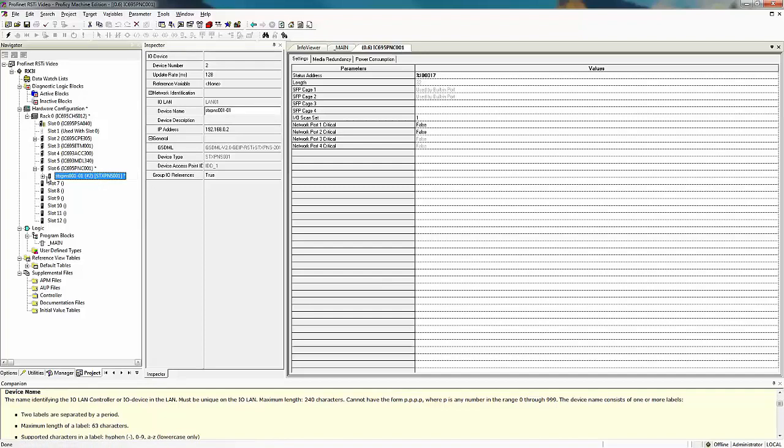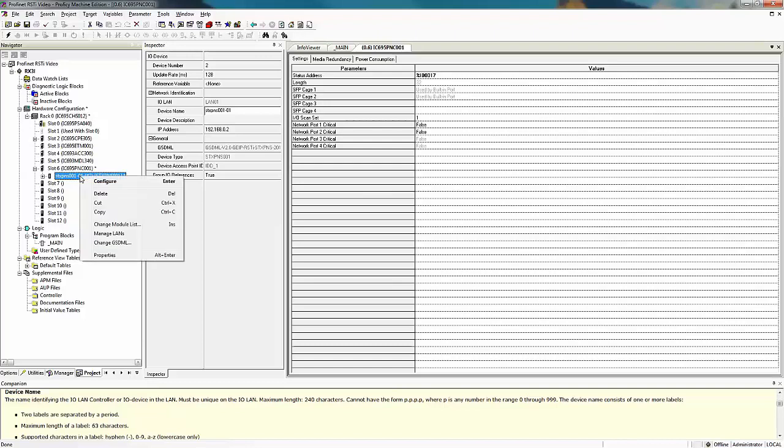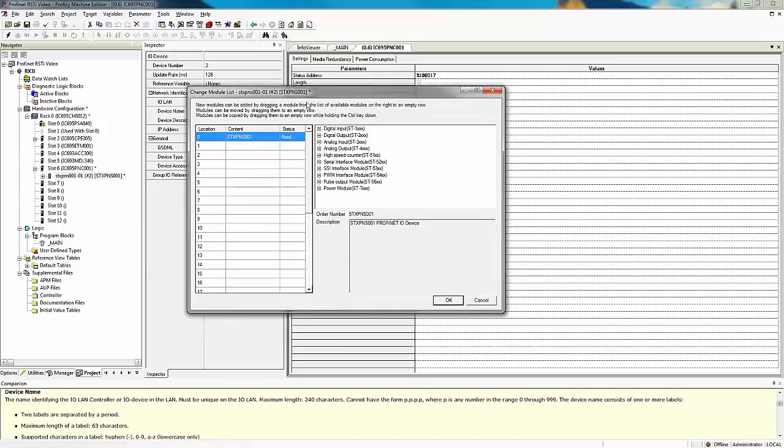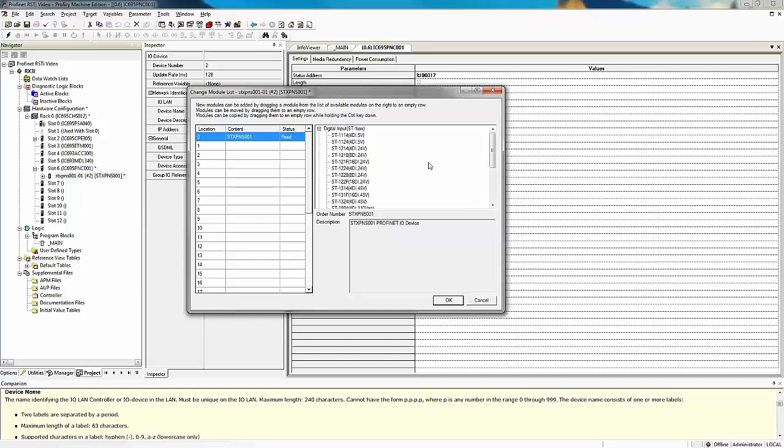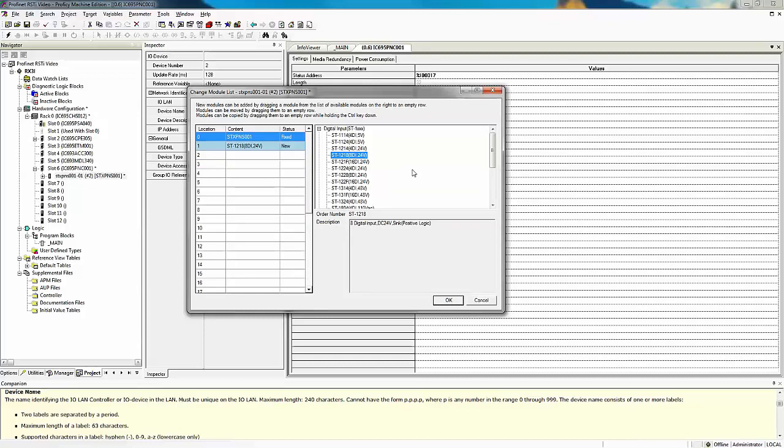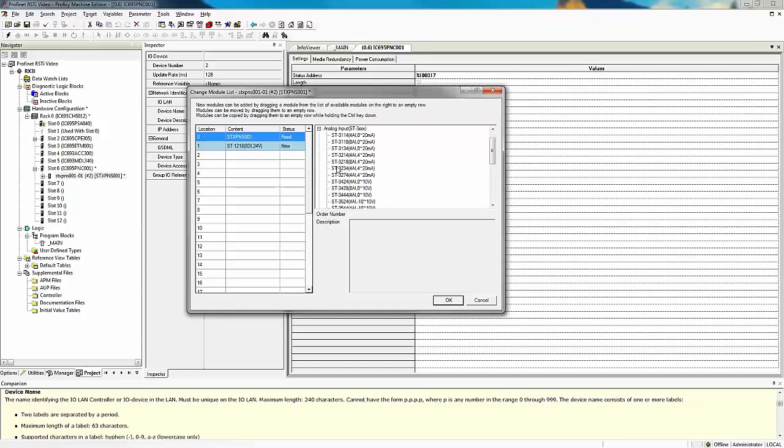From here, we'd like to add the modules or the actual IO to our PROFINET drop. We do this by right clicking on it and choosing change module list. This brings up a list of all the different PROFINET IO modules that are available. Looking back on my PROFINET drop, I have written down the IO modules. My first IO module is a discrete input, model number ST1218, and I simply click on that and drag and drop it into my system. My next module is a 3214, it's an analog input. Here it is, drag and drop it into the system.